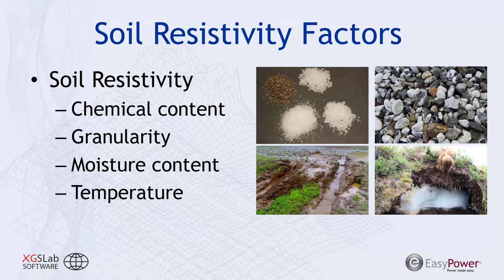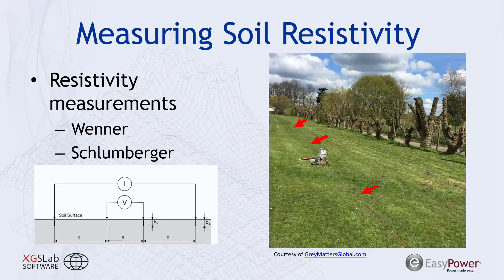When we talk about soil temperature and its effect, we see a dramatic effect at extreme temperatures such as frozen soil. When the soil is frozen, those ions' movement is not free — they get trapped, and that increases resistivity dramatically. Before we get into that, let's talk about how resistivity information is actually acquired.